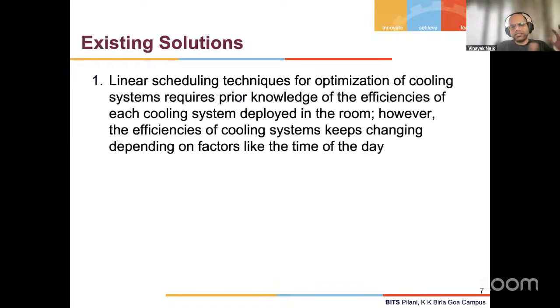So what exists, or what we've tried so far, and what sort of works: one is linear scheduling techniques, where we optimize the cooling system based on prior knowledge of the efficiency of each cooling system. For example, when you buy these ACs new, they come with a manual, a data sheet, which tells us how much cooling impact this AC will do when new. But as you run this AC, the gas gets less, and your setting could be different from where these energy ratings were derived. Still, if you do this calculation once and use these numbers for the whole lifetime of the AC, that solution would work.